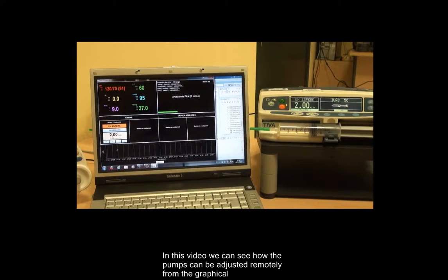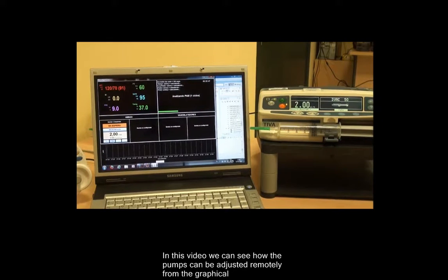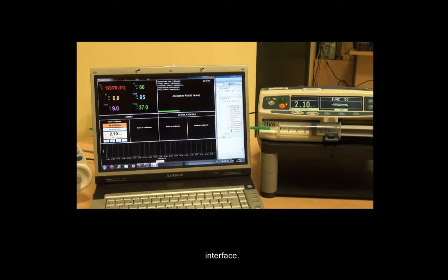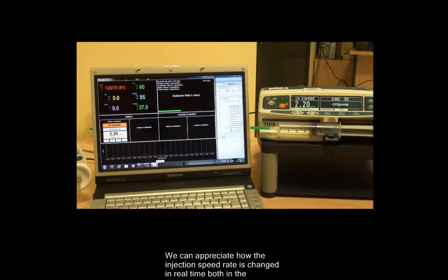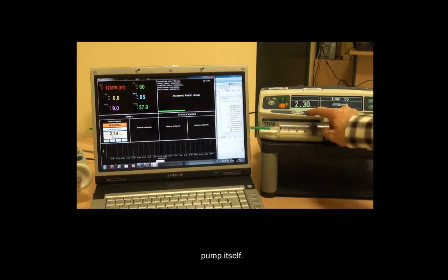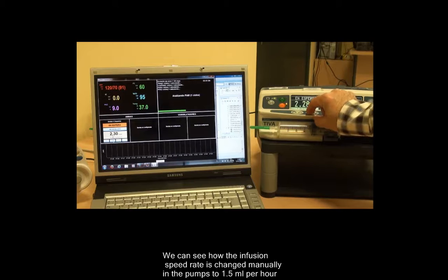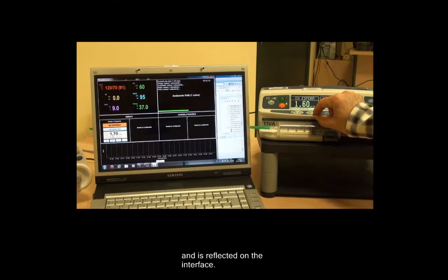In this video, we can see how the pumps can be adjusted remotely from the graphical interface. We can appreciate how the injection speed rate is changed in real time, both in the graphical user interface and in the pump. We are also able to modify them manually by adjusting the injection speed rate from the pump itself. We can see how the infusion speed rate is changed manually in the pumps to 1.5 ml per hour and is reflected in the interface.